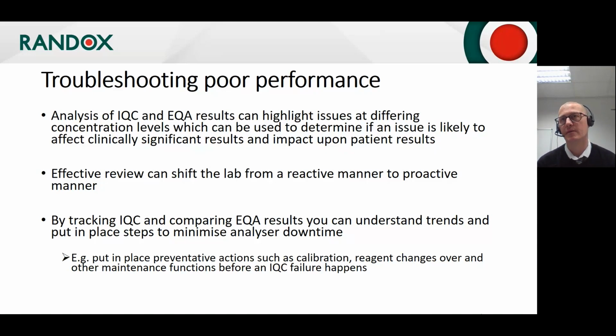If it was at the low end, I'm thinking off the top of my head, CRP. Obviously, if we're looking at CRP, we're looking for raised CRP. So if I've got a problem on a CRP level of less than 3, then I'm not really going to be that worried about it, because ultimately all our results are going to go out as less than 3 anyway. If it were up at the 200 level, then that's when I'd be worrying, because obviously if I'm sending out results that are high CRP greater than 200, but I know my QC's failing or my EQA's shown that I've got a problem at that end, then that does need evaluating and dealing with properly.